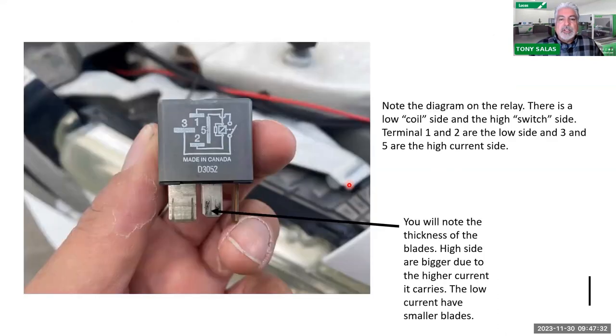So there you go. Now when you look at the relay itself, some relays are pretty awesome. Sticking to that same FICM relay, you can see the contacts right there. So in this case, we see 1, 5, 2, and 3. You could read the diagram itself. There's the contacts right here. So there's 3, and when the contacts close, that goes to 5. So 3 and 5 are the contact side, while the coil side, which is this guy right here, is 1 and 2 - the low current and the high current side. And like I told you already, you'll see the difference in the thickness.